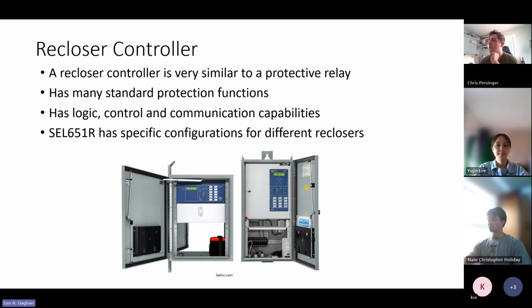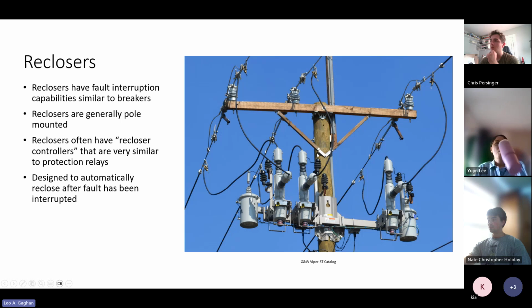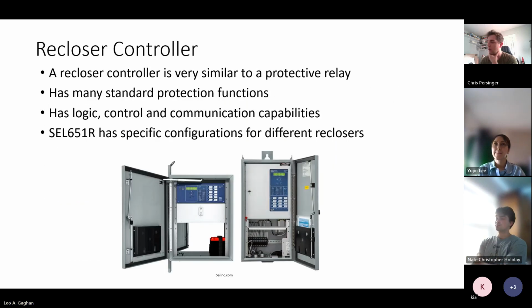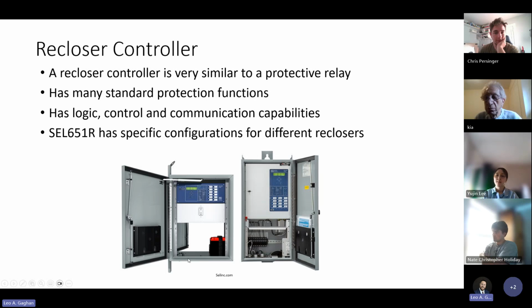This here is a pretty typical recloser controller. This in particular is a 651R. And usually this is how you get them, right? They come in these cabinets from the manufacturer. You can see this one has a mount to put it on a pole. They usually get their power from this voltage up here. You can see we've got a little PT that'll give us voltage. You can also see that if we do lose power, we've got some battery backup, and a few other things for convenience, like an outlet and such.